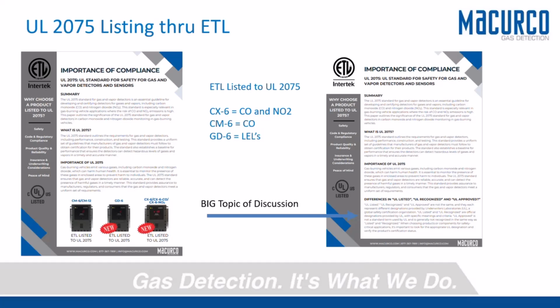I'll give you one case — I won't name manufacturers — but there was a $50,000 gas detection system in Arizona last year that was fully implemented and up and running, and it got ripped out. It got ripped out because it was not UL certified to 2075. They needed both CO and NO2, which this one was not. And they called us to get it installed as quickly as possible. These things are happening all over the country.